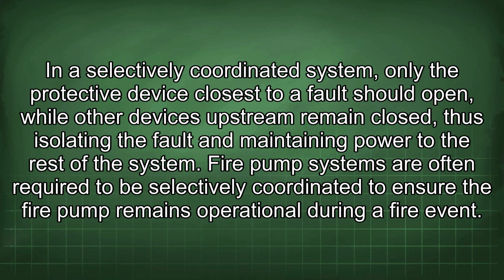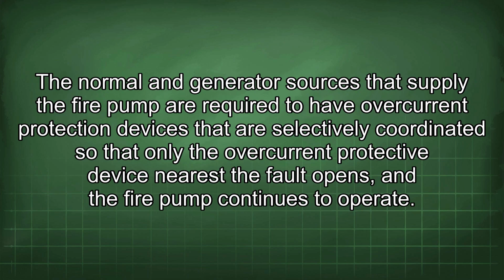Fire pump systems are often required to be selectively coordinated to ensure the fire pump remains operational during a fire event. The normal and generator sources that supply the fire pump are required to have overcurrent protection devices that are selectively coordinated so that only the overcurrent protective device nearest the fault opens and the fire pump continues to operate.